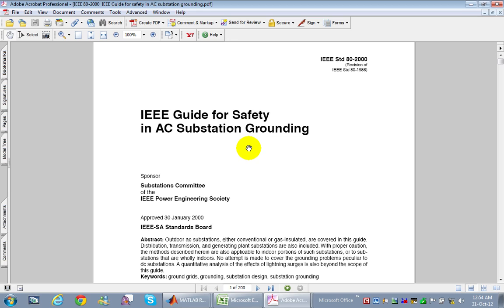After reading the standard, you will find that the starting point for designing a grounding grid for power substations is taking actual measurements of the substation land — specifically the soil resistivity. In theory, we assume the earth has a potential of zero volts, but in reality this is incorrect since the ground consists of many ingredients like soil, rocks, and other materials.